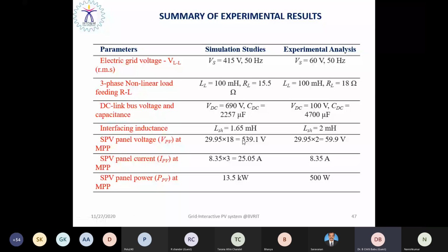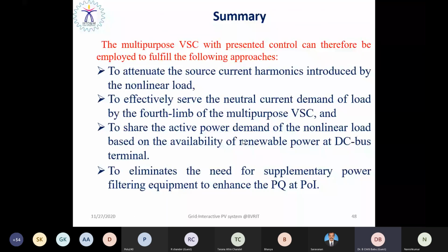In summary, the presented control strategy of the multi-purpose voltage source converter can be made to fulfill the grid connection requirements to integrate the intermittent solar PV system with the utility grid. The requirements include source current harmonic rejection of the harmonics introduced by the nonlinear load, and it effectively serves as the neutral current compensator with the help of the fourth leg.